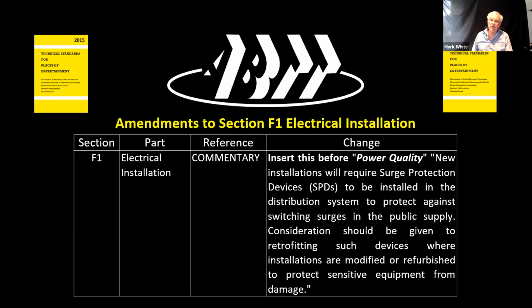The ABTT had its own 2 editions of testing of electrical equipment, and then PAT had a very bad name in terms of being done unnecessarily. In the Löfstedt report into health and safety legislation and the executive, one of the things it said back in 2011 was that portable appliance testing shouldn't be done at fixed intervals - it should always be done on a risk assessment basis to decide whether something actually needs testing.